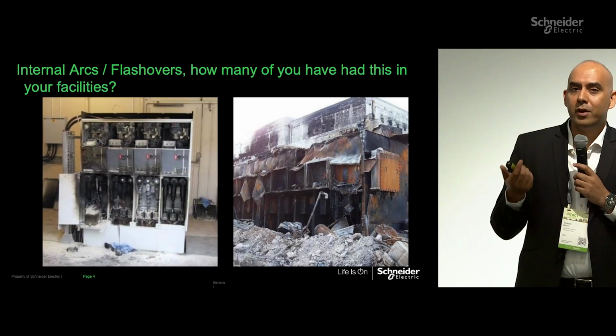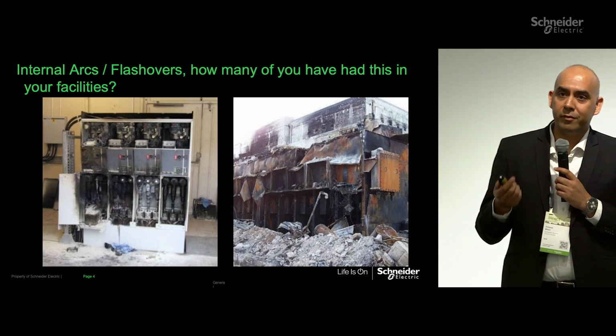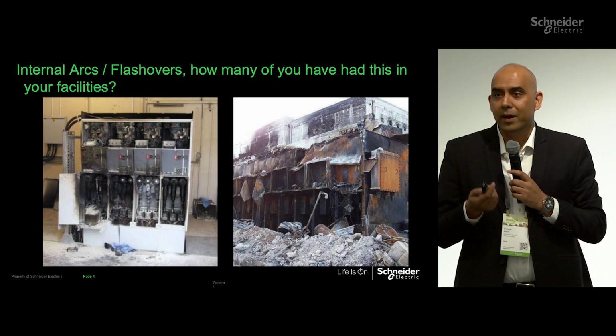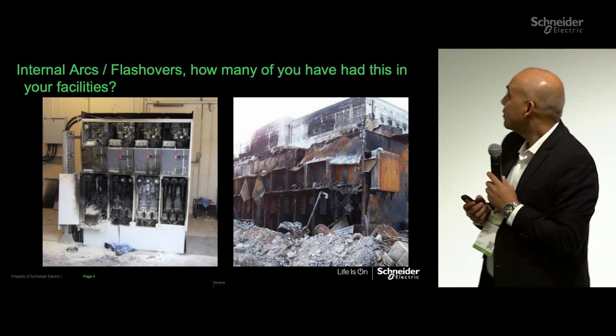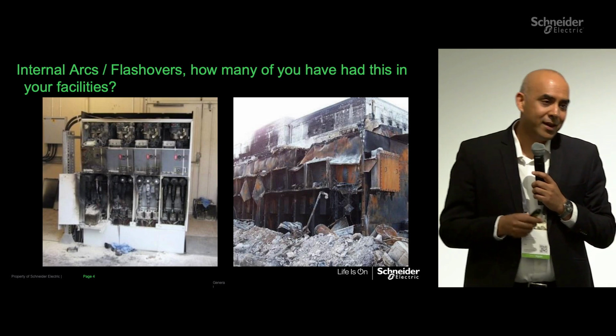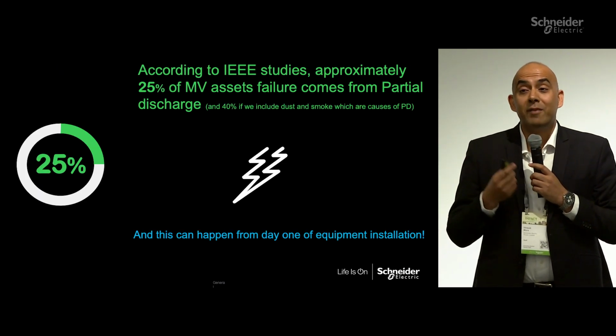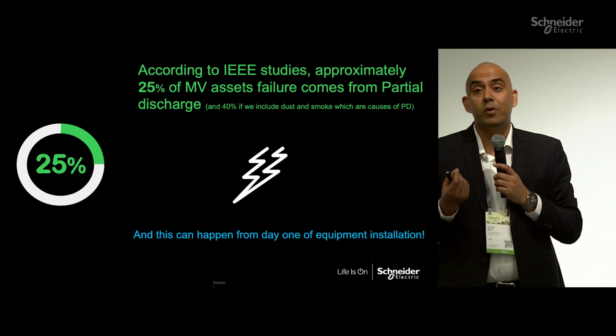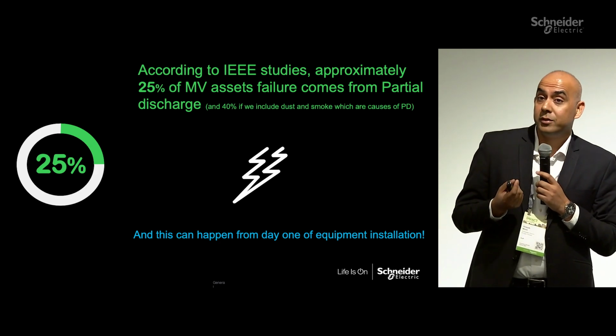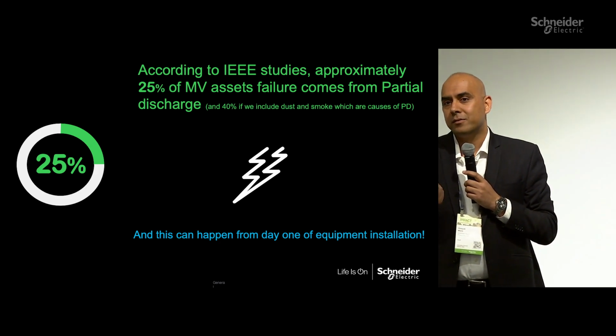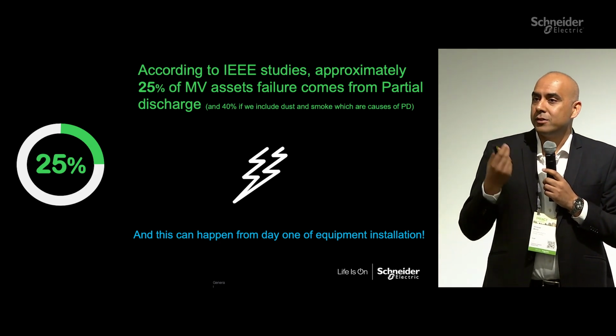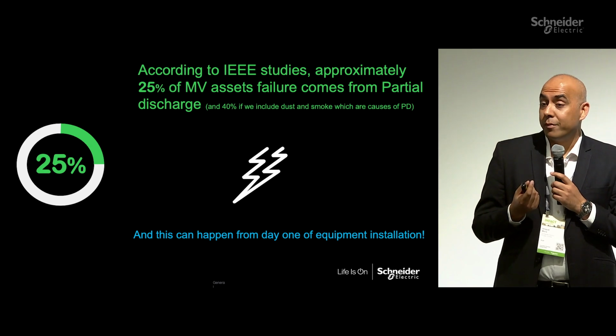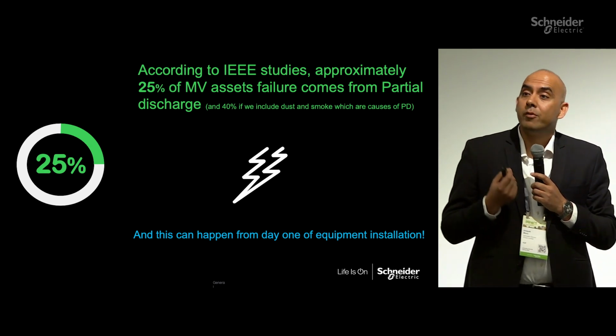These are nothing but the results of partial discharges which have not been monitored and have worsened over a period of time. So what are partial discharges? One fact: 25% of the failures in medium voltage equipment happen due to these partial discharges. And it increases if you have dust or a smoky environment. And it can happen from day one.